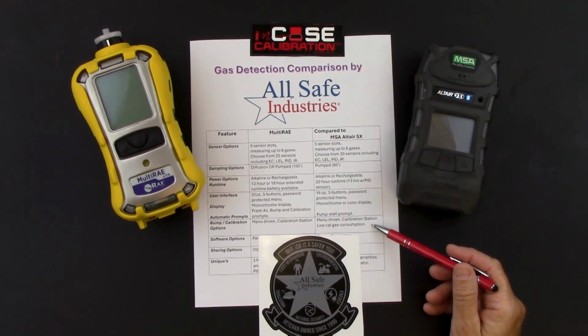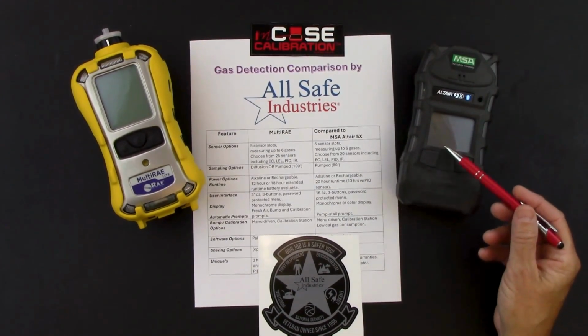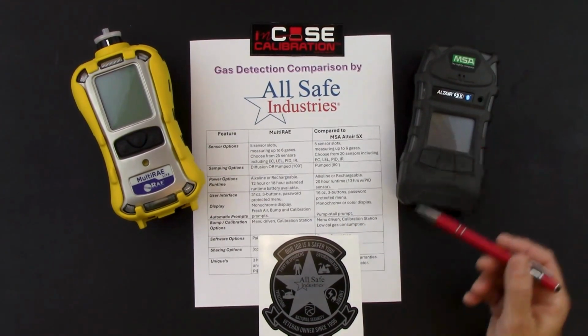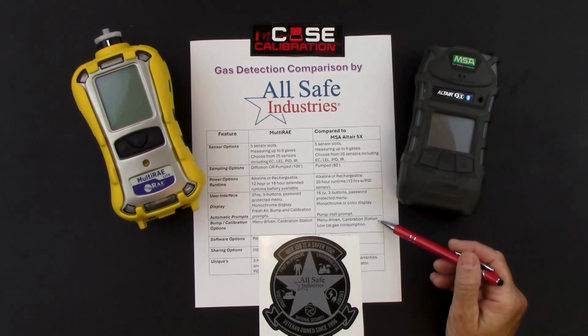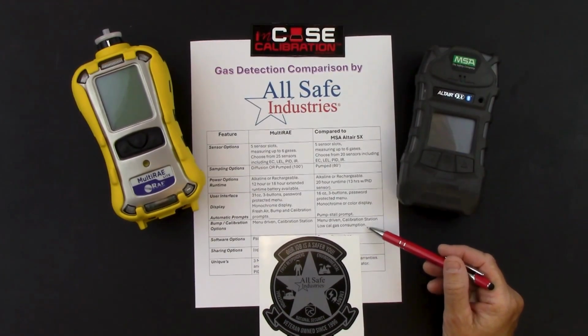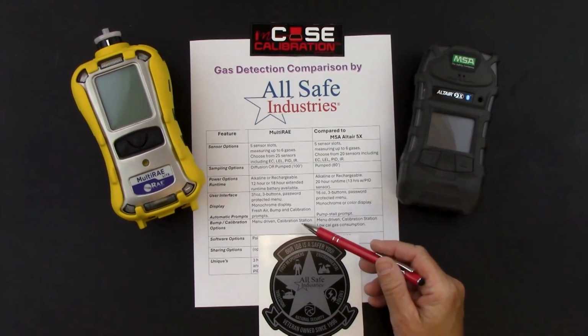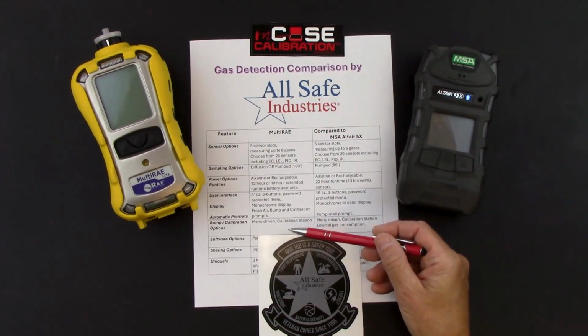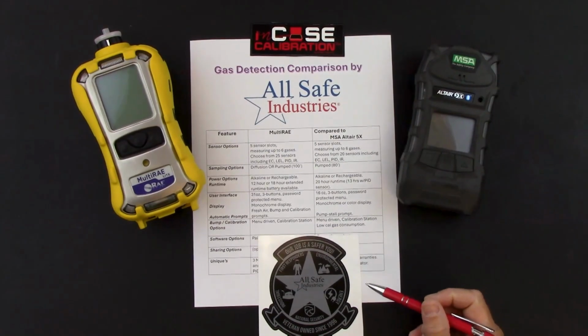With the Altair 5X, we have the same choices. We can perform bump checks and calibrations right from the screen of the instrument. We can also use the Galaxy 2 calibration station to perform those tests automatically. And then one of the features with MSA is it is very low cal gas consumption when we're doing bump checks and calibrations, because it uses a 1/4 liter per minute regulator versus a 1/2 liter and sometimes a full liter of flow for cal gas on the MultiRAE.